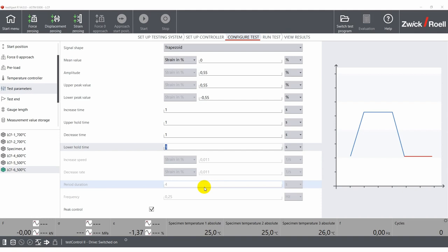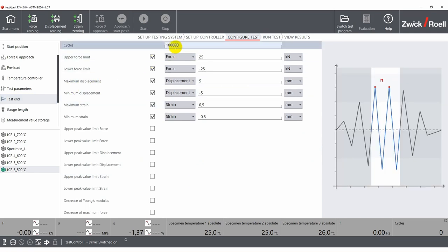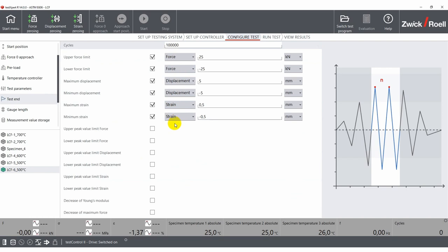After that, you have to define an end criteria for your test. There are two ways in which the test can end. Either your specimen reaches the target cycle count without breaking, or it breaks before reaching that given number. In this case, it will hit one of the set limits, which can be defined by the user.